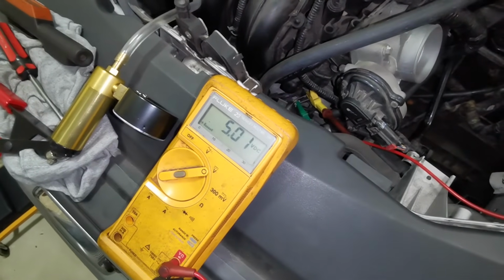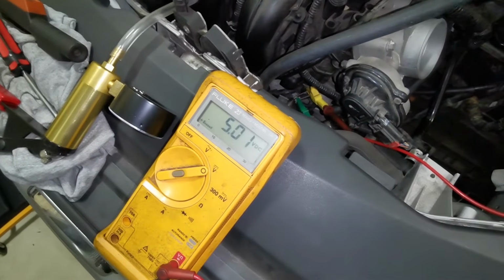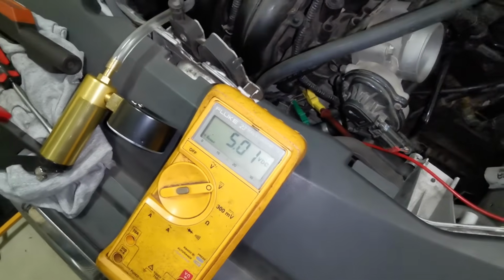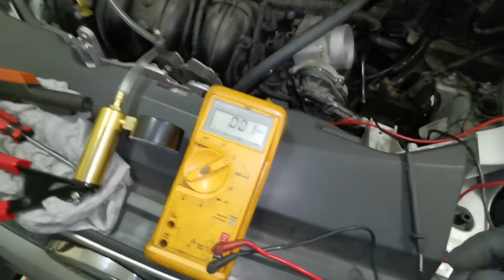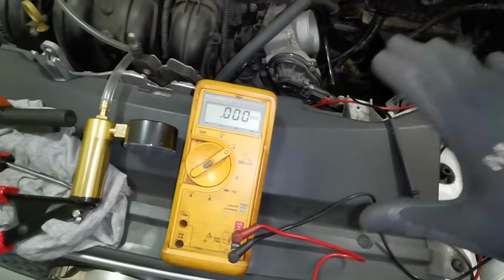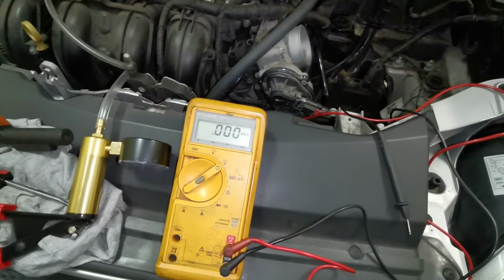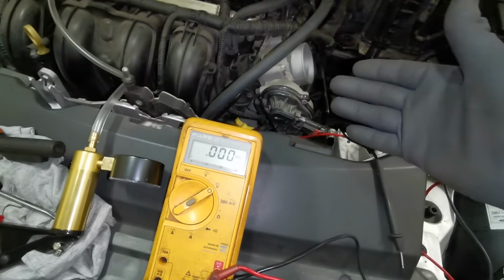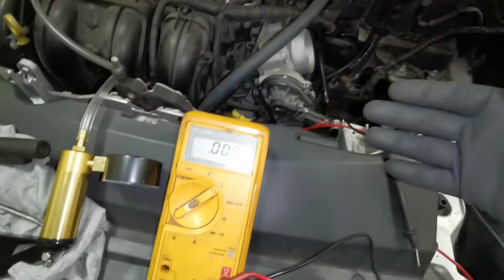So like I said, on that 5 volt reference, anything between 4.8 and 5.2 is absolutely fine, and that is how you test it. That is how you know if you've got correct voltage going down to it, if you have a correct reading using a vacuum gauge.